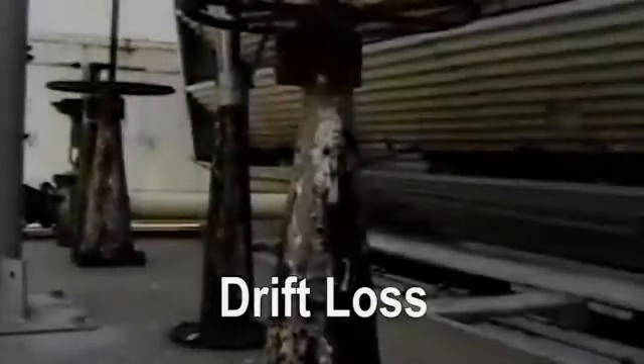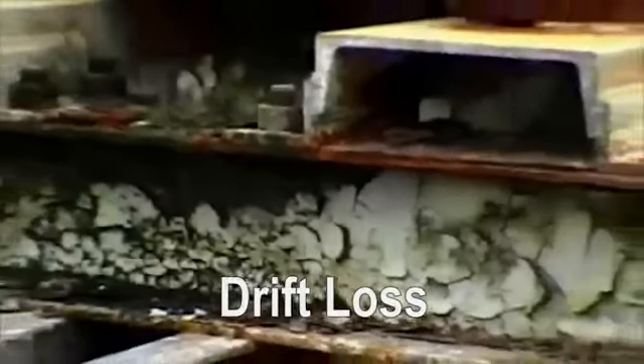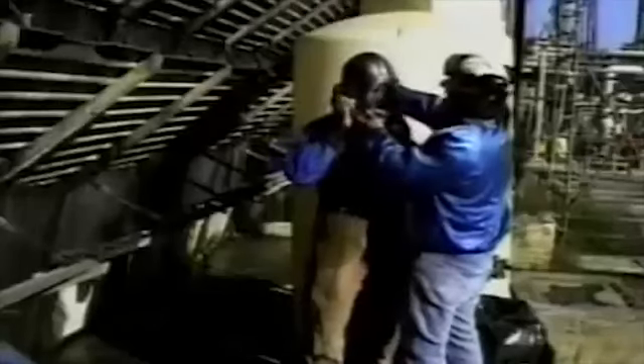In most facilities, makeup water is as precious as fuel. Increased drift loss also corrodes and contaminates adjacent equipment. In areas where water loading is light, evaporation accelerates, causing premature fouling of the film media.